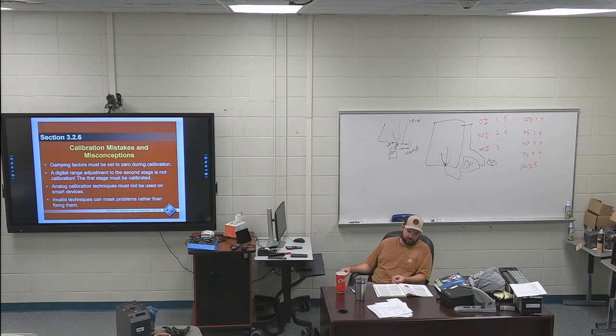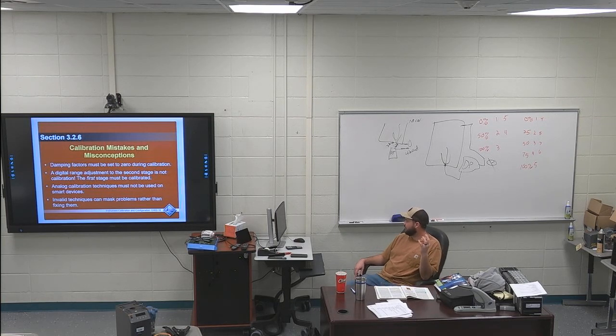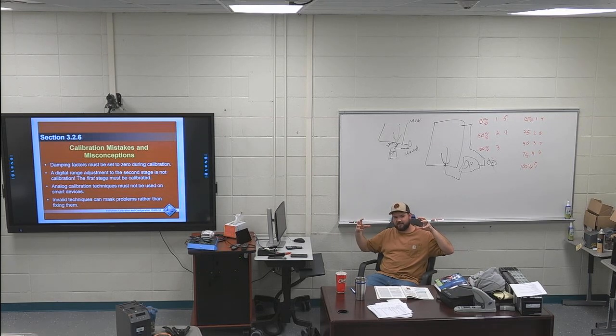Why would you want to do this? Why would you want a delay, when you have your three different sections, like your input side, middle side, output side, and you make a calibration? To stabilize it, to make it more stable. Right. Because if you changed it immediately, as soon as it goes up, the output stage is going to do this. Dampening is going to let you have a little bit smoother curves and stuff like that.